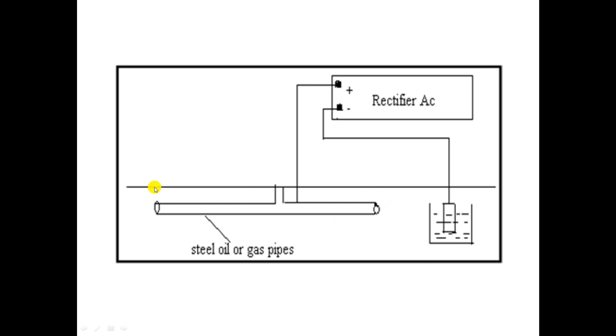Consider an iron or steel pipe inside moisture-containing soil, which will easily undergo corrosion. When the iron undergoes corrosion, it undergoes oxidation and produces electrons — these electrons reach the cathode, generating what we call a corrosion current. By using a battery, we apply a sufficient amount of current to suppress and nullify this corrosion current, making the iron act as a cathode. The negative terminal of the battery is connected to the more stable anode — here, graphite is used as the anode — and the steel pipe becomes the cathode. By passing a certain amount of current, the corrosion current is nullified and the metal is protected from corrosion.